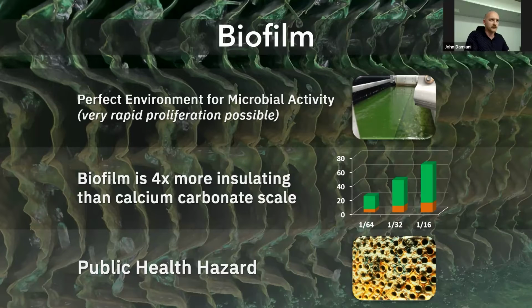So biofilm is when specific types of bacteria will actually form a film on the surface. And one thing a lot of people don't know is that a lot of people are worried about scale, and they should be, calcium carbonate scale, for example. But biofilm is actually 4 times more insulating than calcium carbonate scale.